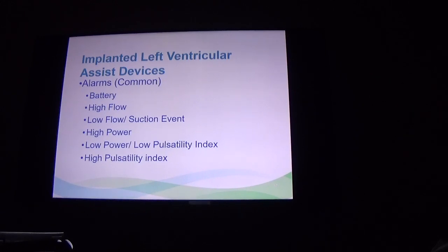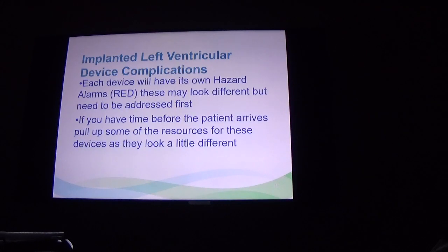So common alarms that you're going to see are just right here. Again, battery is probably the most important one. Make sure you're plugged into AC mode anytime the patient's in an ER. If they're in the waiting room, for some reason, maybe they broke their leg and you think, hey, this person has an LVAD, let's at least get them somewhere where they can plug in, because they only have so much time on those batteries. High flow, low flow, power, pulsatility index, we'll discuss all these as we go.